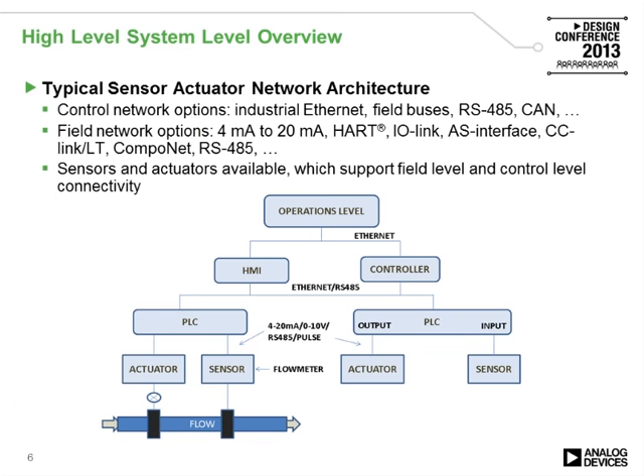So a high-level system-level overview: we have a sensor connected to our PLC, and our PLC will also be connected to an actuator. In this diagram, we're controlling the flow based on the flow sensor measurement. In terms of communications protocol between the PLC and sensor/actuator, often 4 to 20 milliamp loops, could be a 0 to 10 volt connection, or else some sort of fieldbus RS485 type protocol. Then from the PLC back to the controller, we might have some Ethernet or else a fieldbus protocol. From the controller back to the operations level, it's almost exclusively Ethernet.